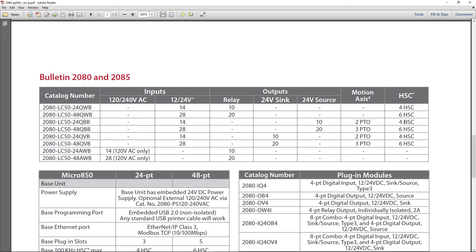And the reason for this is that the high-speed counter inputs and the pulse train output outputs, if those screw terminals have special electronics. So for instance, let's take a high-speed counter. The high-speed counter counts the false-to-true transitions coming to the screw terminal, but it can do it at a rate much faster than the IO scan rate of the controller.